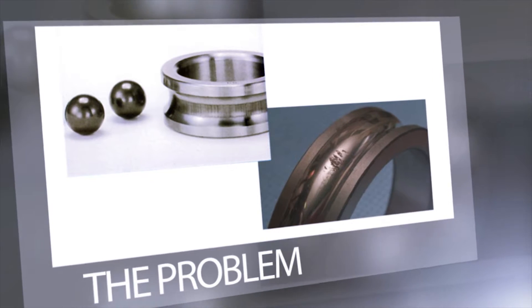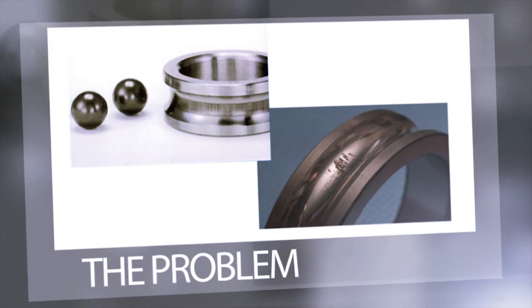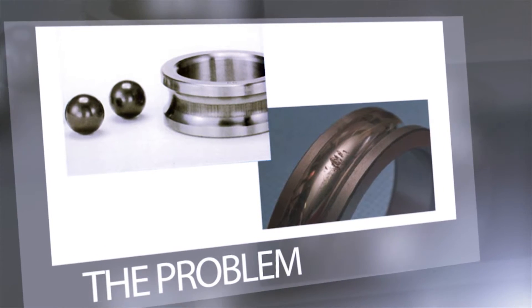A problem concerning all electric motors with VFDs, also known as inverter output, is the bearing damage and circulating currents caused by high-frequency currents the VFDs produce, resulting in pitting, fluting, frosting of bearings, and lubrication breakdown. This destruction of the bearing can now be virtually eliminated.